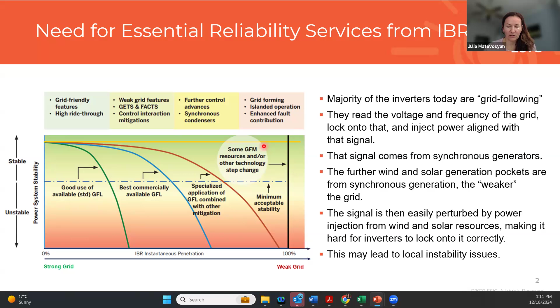And so system operators go for these support measures to maintain the grid stable as penetrations of grid following inverter-based resources are growing. And as we start to progress, maybe I would say the last 20%, it depends on the grid, but around the last 20% of penetration from inverter-based resources, this is where we start to look at even further control advancements from inverter-based resources, and this is where grid forming comes in. So this is a new type of control for grid-connected inverter-based resources where they behave more like a strong voltage source, in a somewhat similar manner to synchronous generators. And having some percentage of this type of resources on the grid would allow us to get to 100% inverter-based penetration. So theoretically, and also there are island grids where you can get to 100% penetration with just inverter-based resources, and you don't need synchronous machines, potentially.